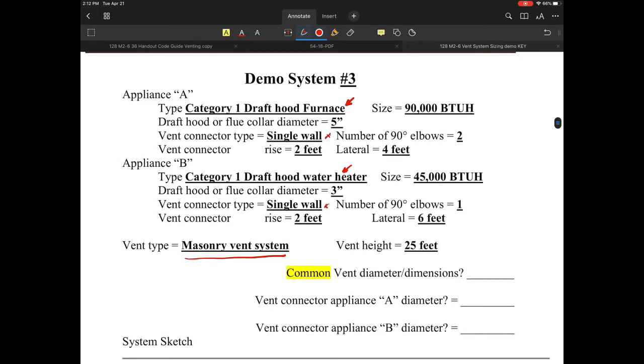We're going to have single wall vent connectors. For elbows, I've got two and one — since there's only one, I don't add anything at all. We have a rise of two feet for each of these, a lateral of four feet, and a lateral of six. We're definitely going to want to watch the laterals to make sure we are not overextended, in case we need to look at any D-rating or possibly increasing the size of the vent system because of the excessive lateral.